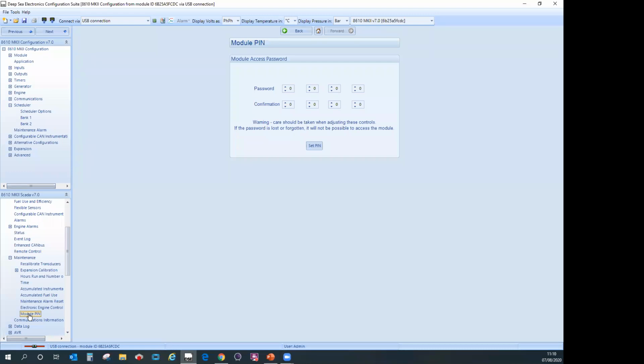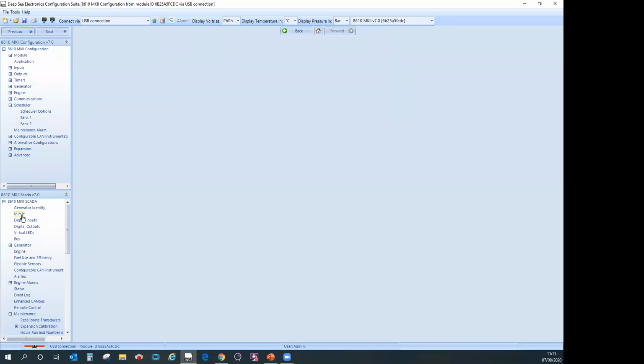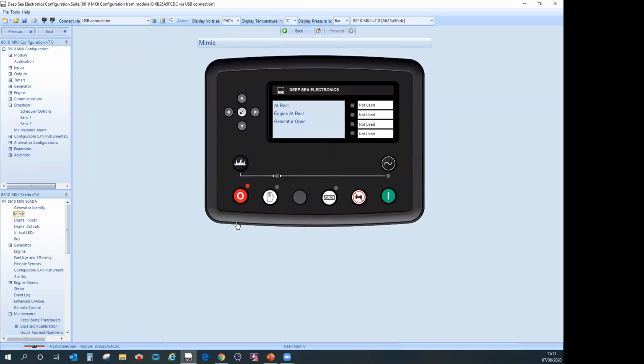Okay, so I'm not going to get too much more into Config Suite. I think the final thing I'm going to show you is what the actual buttons do. It's a very common question: what do the actual buttons do? So if we go back to the Mimic, we've got the stop button here. Okay, it puts the controller in stop mode. Whenever it's in stop mode, you can't start the generator. Makes sense? So if someone has a remote input to the controller and wants to start the generator, either via a key switch or a switch in another room, if it's in stop mode, the generator won't start. Okay, and I'm going to skip along to auto mode now.